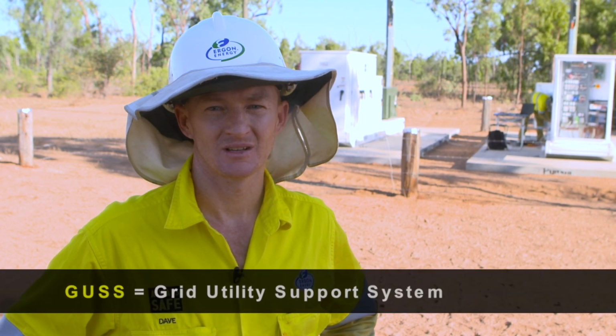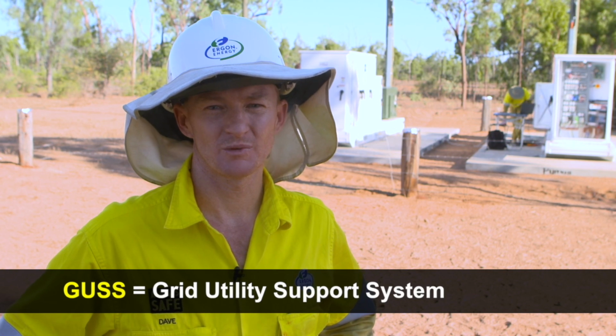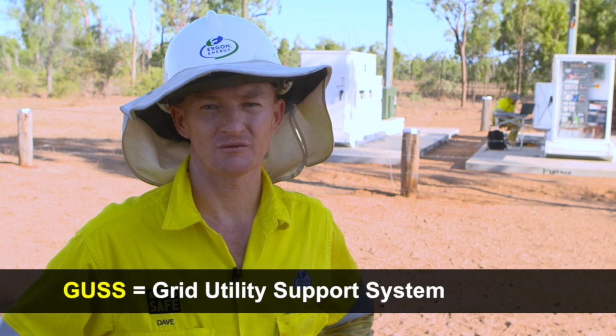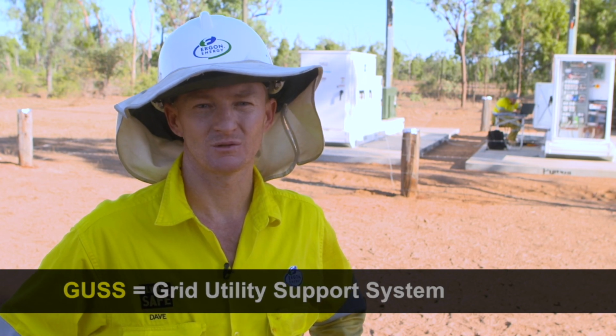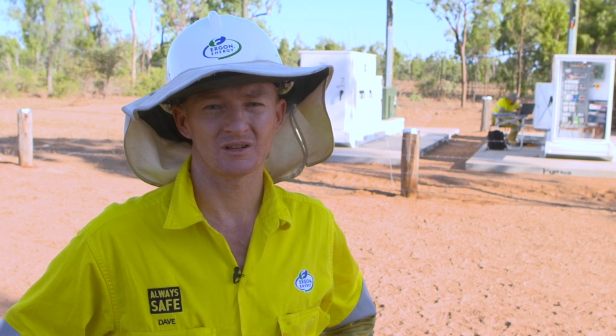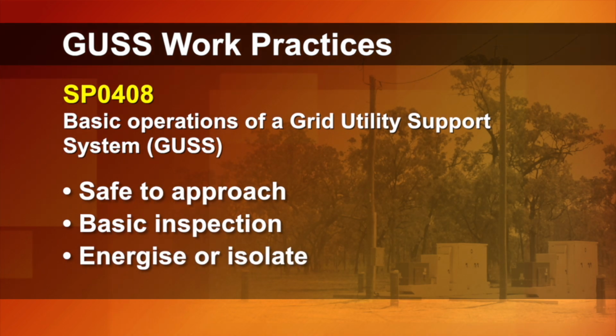Over the coming months, GUSSs will be installed in regional areas across Queensland as part of the project. An induction for depot employees will be conducted close to the installation date for each area. So let's take a look at what will impact you and what you need to know. To begin with, a new SWP has been released, which prescribes the method to safely approach, perform a basic inspection and energise or isolate an in-service GUSS unit.